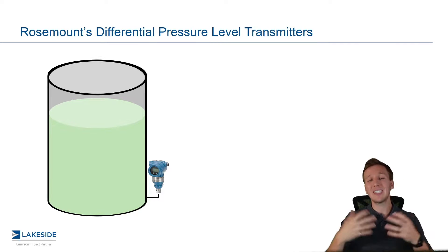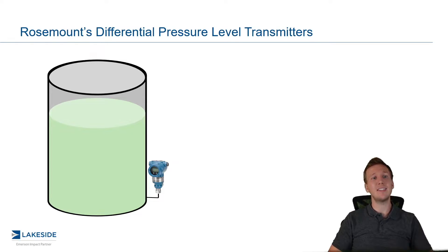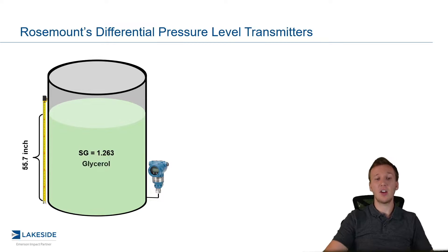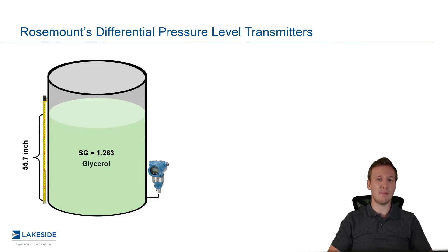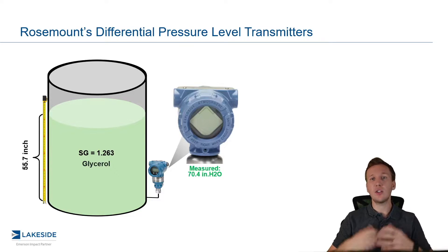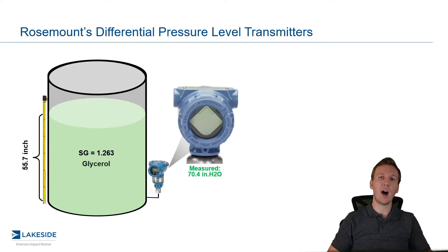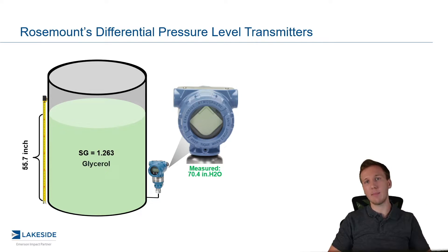If we look at one of the most simple applications, it is an open to air or a vented vessel. What this means is all we have is atmospheric pressure above the liquid. In this case, let's say we have 55.7 inches of glycerol. I picked glycerol because it is denser than water, so it's going to make these calculations a bit more fun. Now if we look at what the gauge pressure transmitter is reading, it's going to read 70.4 inches of water. Now we don't have water, we have glycerol. This is why we are reading a measurement greater than what is actually the volume occupying this vessel.